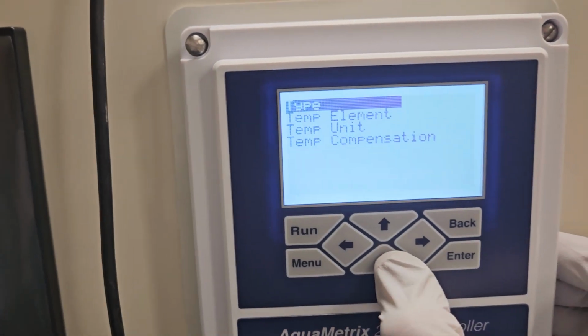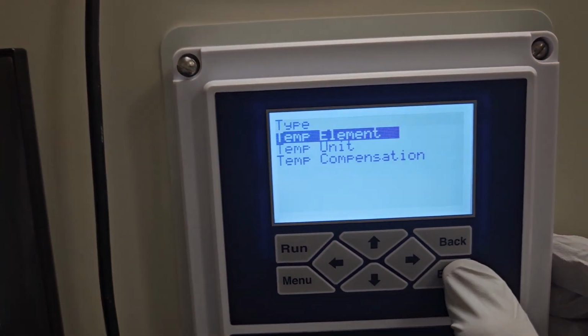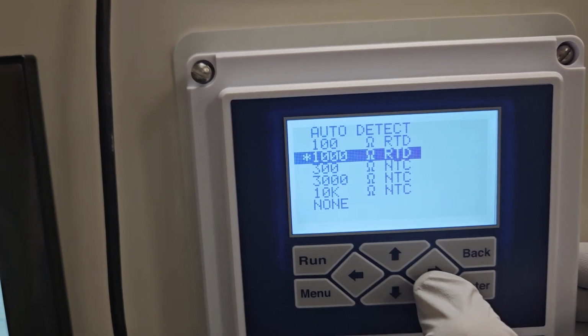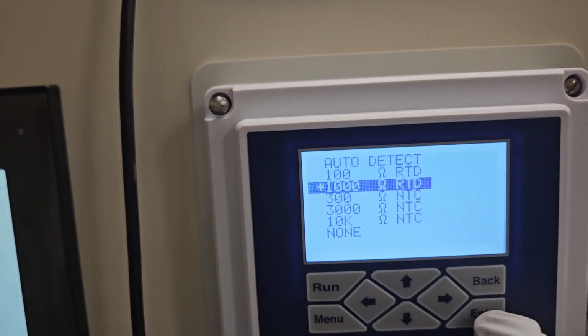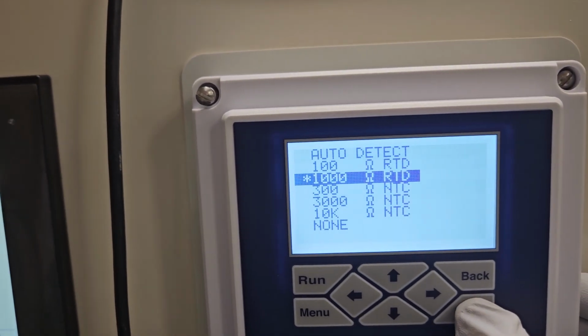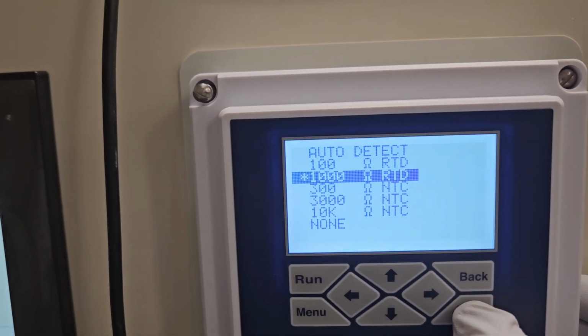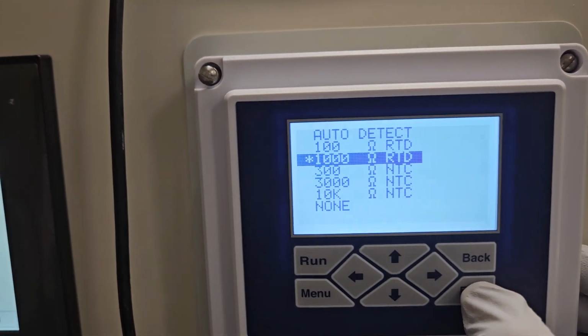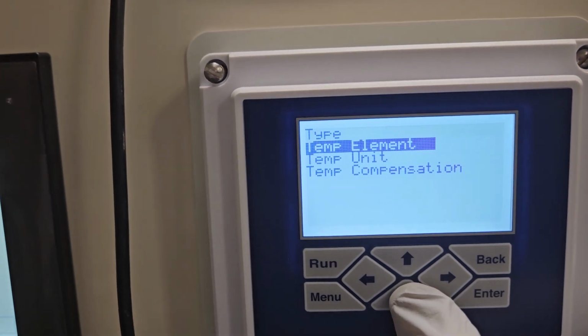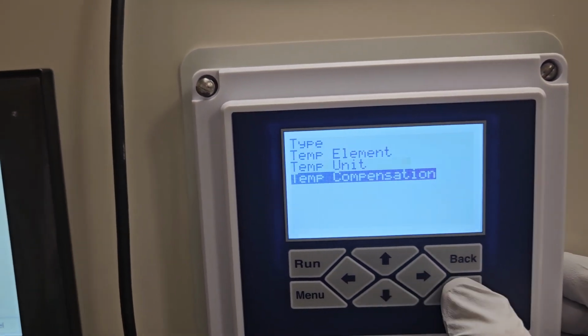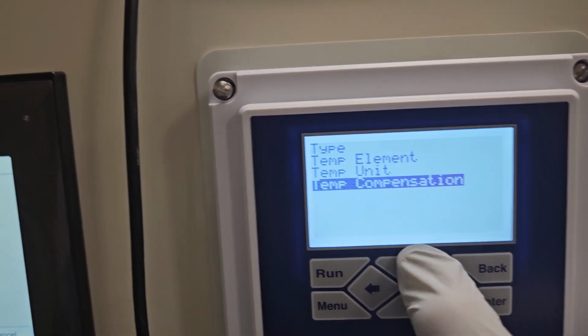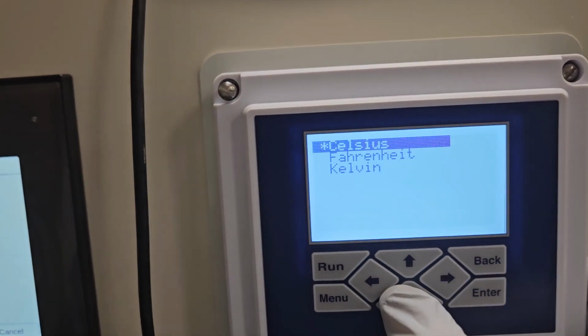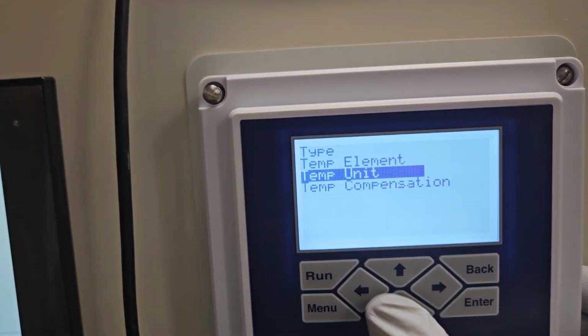The type of it, the element, this is an AquaMetrix water analytics probe. Should be the 1000 ohms is the temperature element setting. If it was a Sensorex or Hach, it would be 300. So 1000 is correct. The temperature compensation should be on. Temperature unit could be in Celsius or Fahrenheit, so we're going to set it to Fahrenheit.